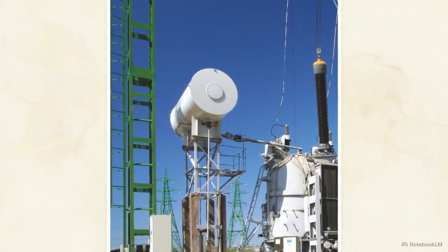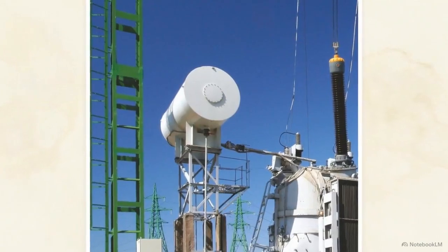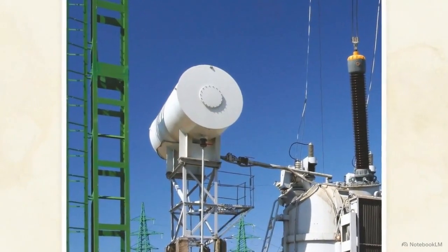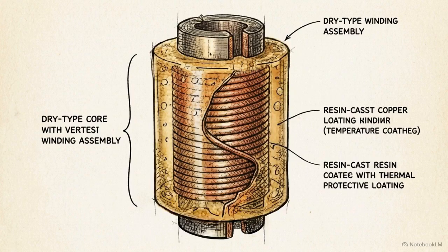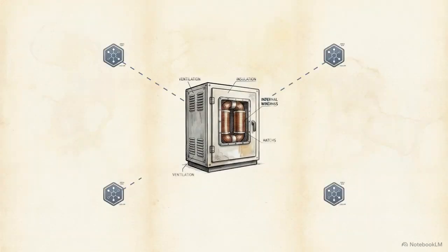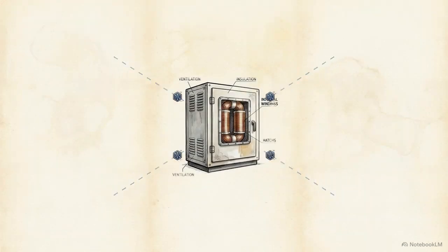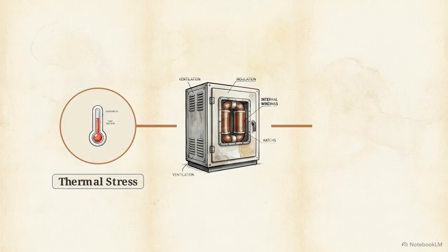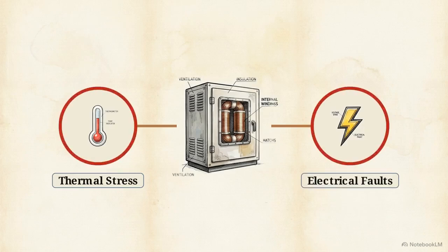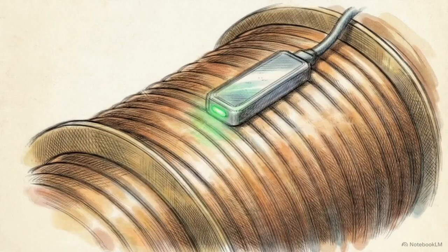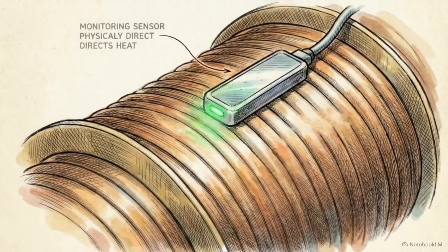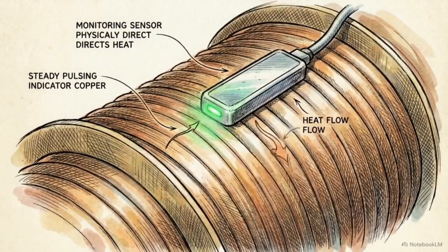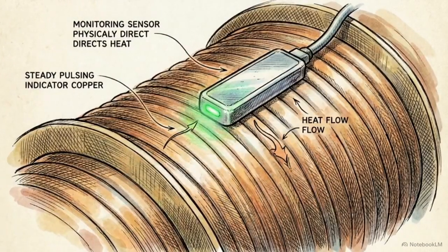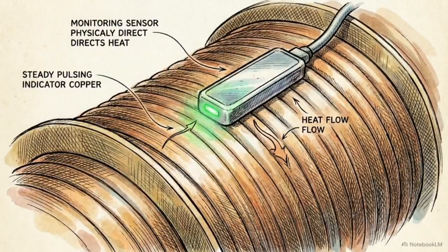Oil-filled units rely on these large overhead conservator tanks and gas detection relays to spot trouble. Dry-type units lack these oil-handling components entirely. Without insulating fluid or gas detectors to provide early warnings, our primary threat vectors narrow down to internal heat generation and direct electrical faults. Because dry-type units lack fluid cooling, configuring proactive, direct monitoring on the coils themselves is our only method to prevent total asset destruction.